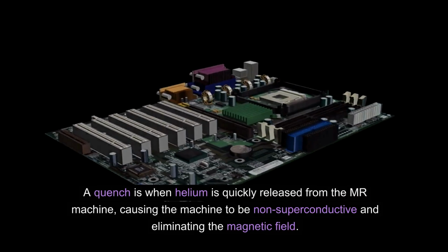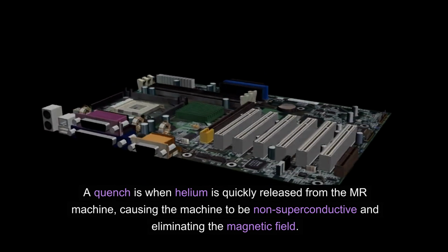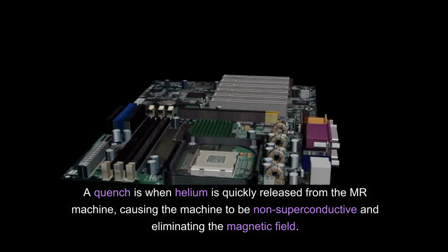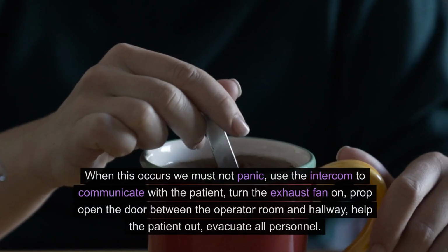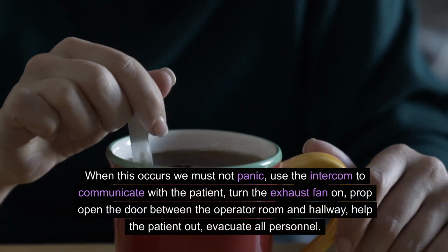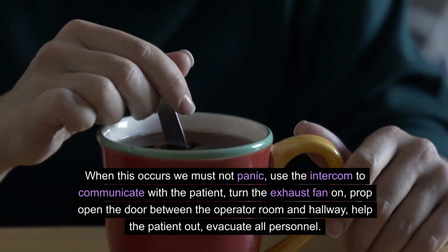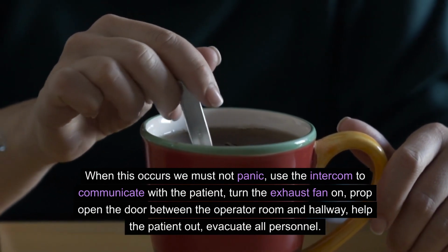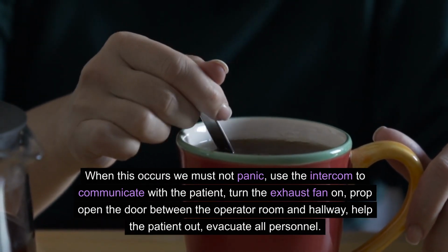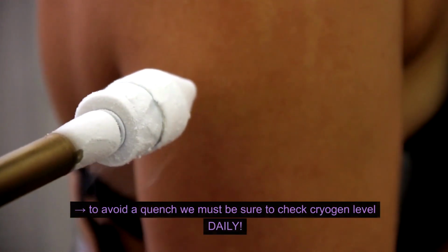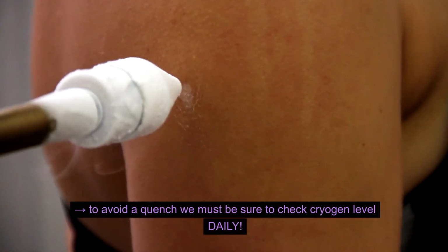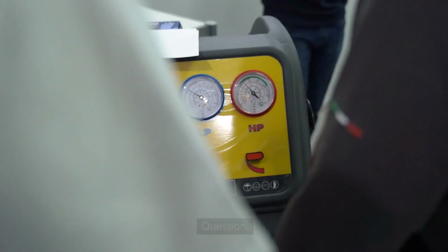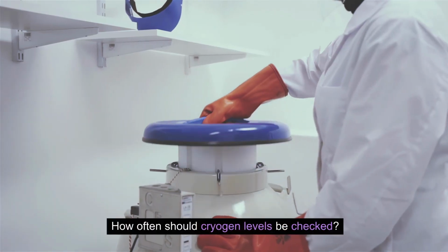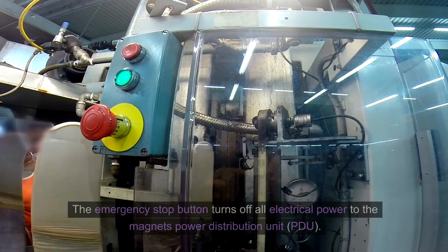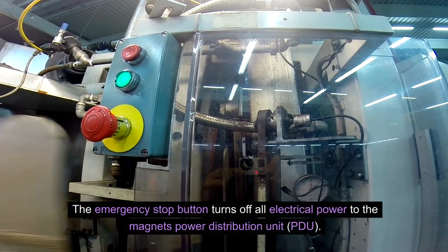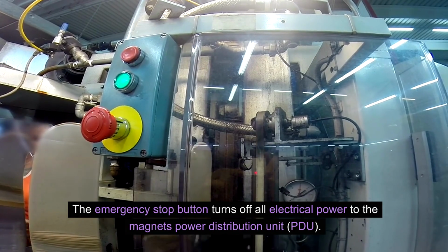A quench is when helium is quickly released from the MR machine, causing the machine to be non-superconductive and eliminating the magnetic field. When this occurs, we must not panic. Use the intercom to communicate with the patient. Turn the exhaust fan on. Prop open the door between the operator room and hallway. Help the patient out. Evacuate all personnel. To avoid a quench, we must be sure to check cryogen level daily. Question: how often should cryogen levels be checked? Answer: daily.